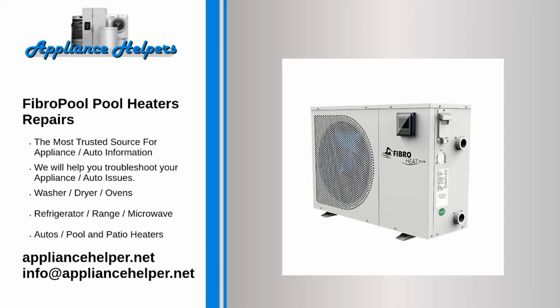Enough water flow. Like other pool heaters, pool heat pumps require a certain amount of water flowing through them for proper heat transfer. If the water is flowing too slowly, it simply won't turn on. Be sure that the water level in the pool is correct, the filter and baskets are clean, and the pump is running fully primed, to provide enough water flow to keep the heater pressure switch or flow switch in the closed position. The heater panel may display flow as an error code when water flow is insufficient.